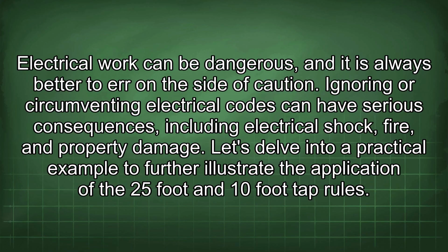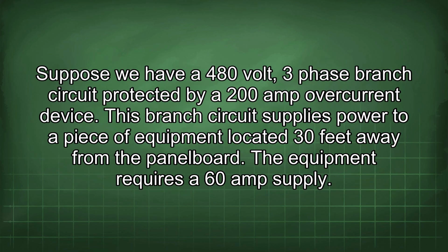Let's delve into a practical example to further illustrate the application of the 25-foot and 10-foot tap rules. Suppose we have a 480-volt, three-phase branch circuit protected by a 200-amp overcurrent device. This branch circuit supplies power to a piece of equipment located 30 feet away from the panel board. The equipment requires a 60-amp supply.